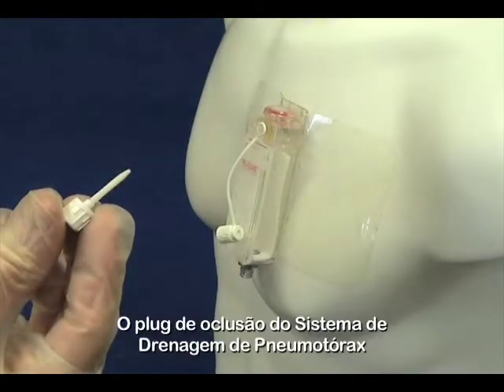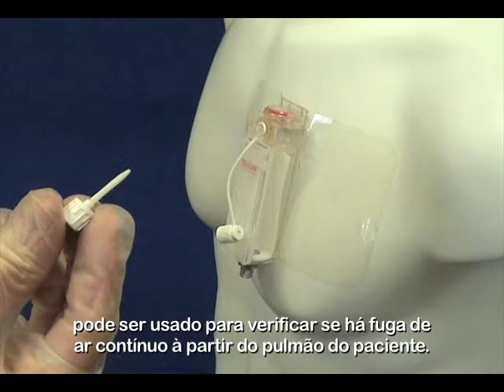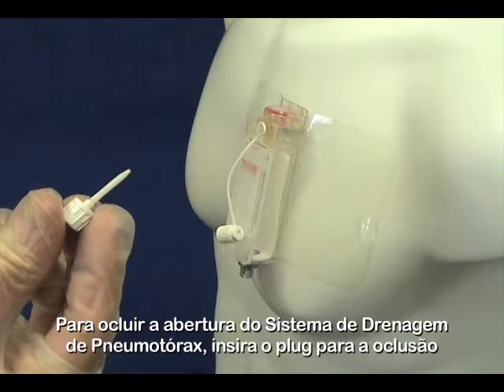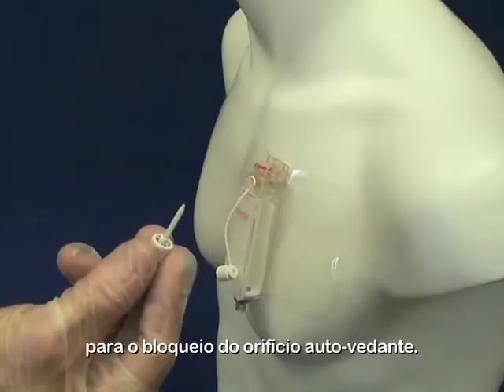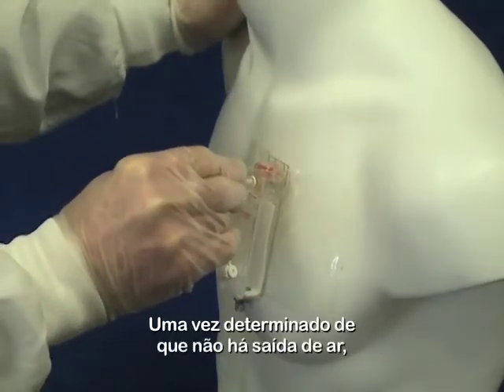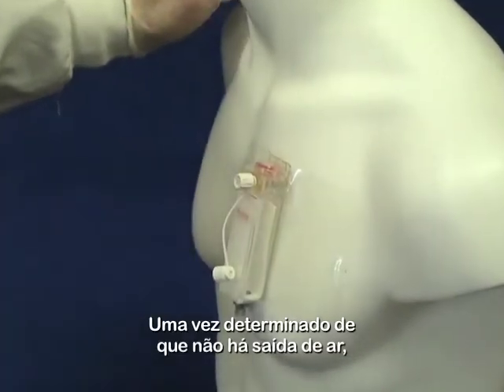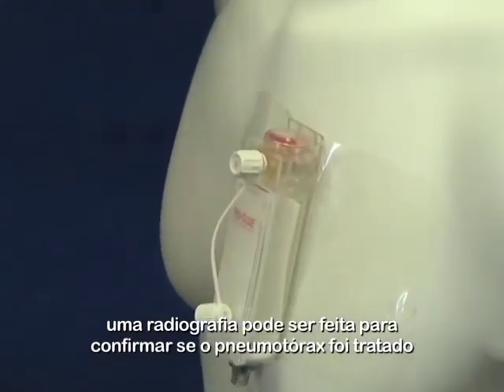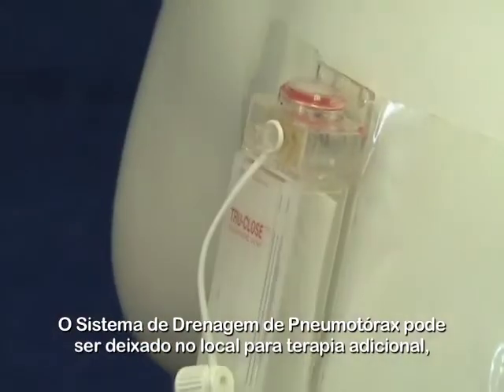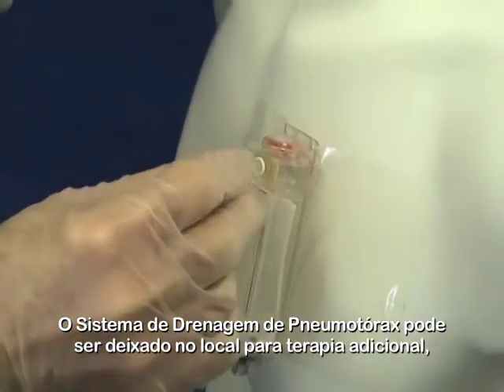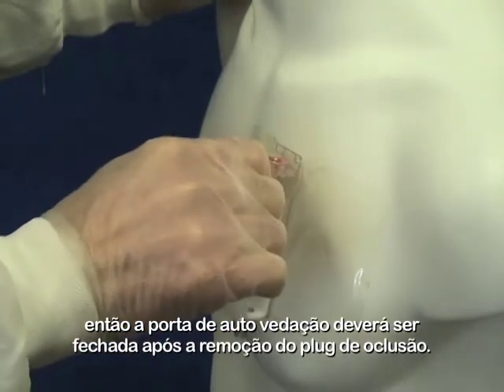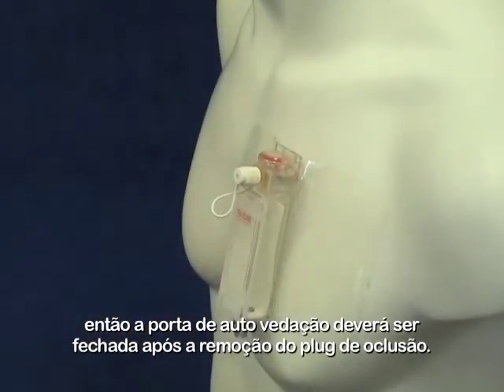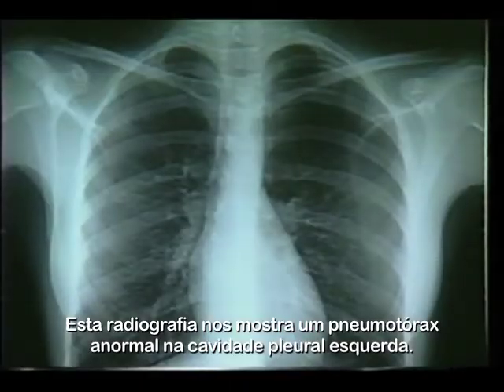The thoracic vent occlusion plug can be used to check for a continuous air leak from the patient's lung. To occlude the thoracic vent, insert and secure the occlusion plug to the Luer lock on the self-sealing port. Once the physician determines that there is no continuous air leak present, then a radiograph can be used to confirm resolution of the pneumothorax, and the vent can be removed. If the vent is to be left in place for further therapy, then the self-sealing port must be covered with the tethered cap after removing the occlusion plug. This radiograph shows a moderate pneumothorax in the left pleural cavity.